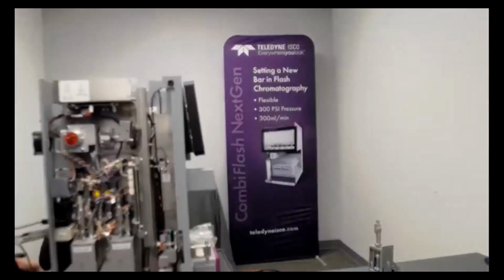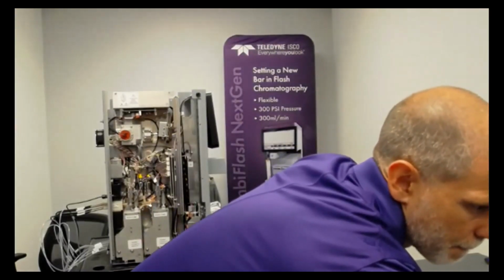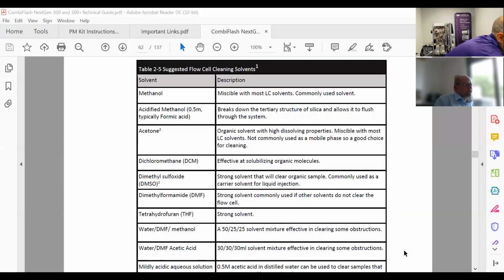And so before I go on to the actual PM, I'm gonna share my screen real quick. So I want you to see something from the manual here. All right, now what we're looking at here are the suggested flow cell cleaning solvents. When you look at this table, it's telling you what solvents we recommend and what they're good for. And again, the two that I touched on were methanol at the top there and acetone that's a couple down.